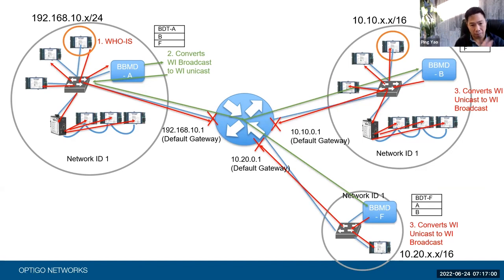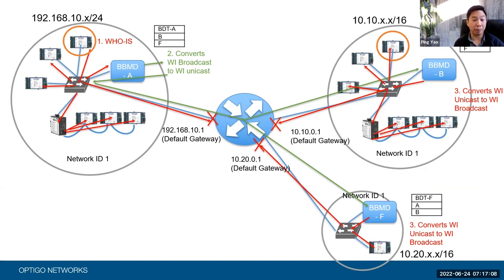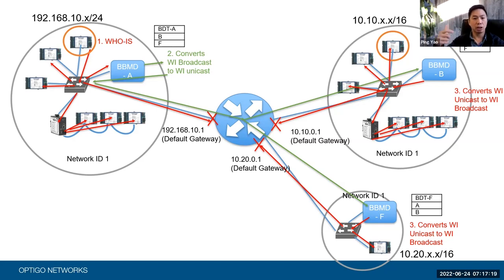It takes a BACnet broadcast message, converts it into unicast, and when it receives a unicast BACnet broadcast sent by one of its peers, it converts it back into broadcast. There are two functions. They call it two-hop broadcast distribution. The first hop goes from broadcast to unicast. The second hop goes from unicast back to broadcast.